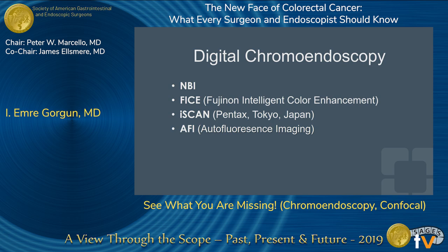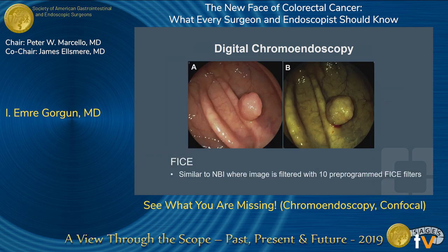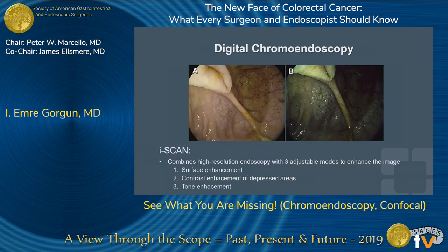Digital chromoendoscopy allows the same endoscopic assessment without giving any actual dye. These include NBI, FICE, iSCAN, or autofluorescent imaging. NBI uses filtered light to increase blue light and decrease red light, narrowing the white light bandwidth, which enhances tissue microvasculature and makes lesions much easier to pick up. FICE is the Fuji equivalent — similar to NBI but filtered with 10 pre-programmed filters and a little more yellow. iSCAN is the Pentax system, combining high-resolution endoscopy with three adjustable modes: surface enhancement, contrast enhancement of depressed areas, and tone enhancement.